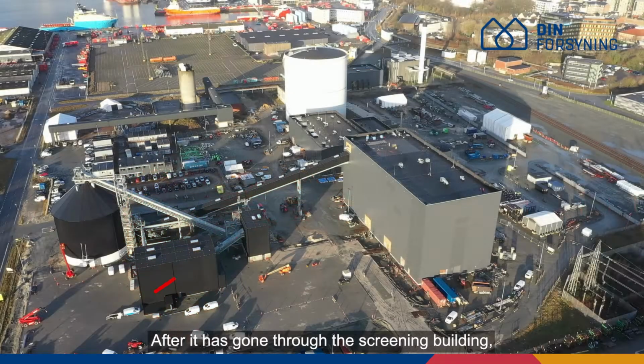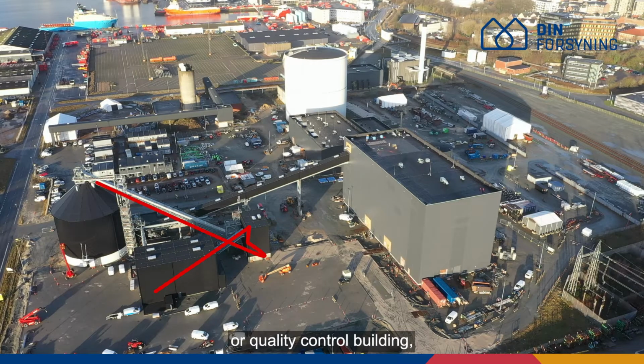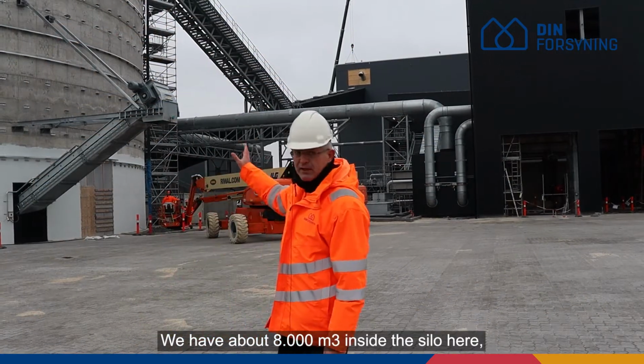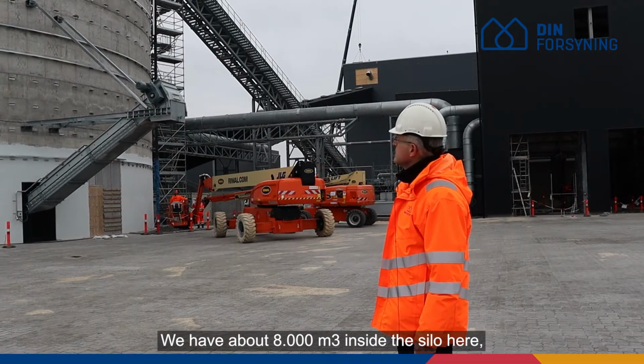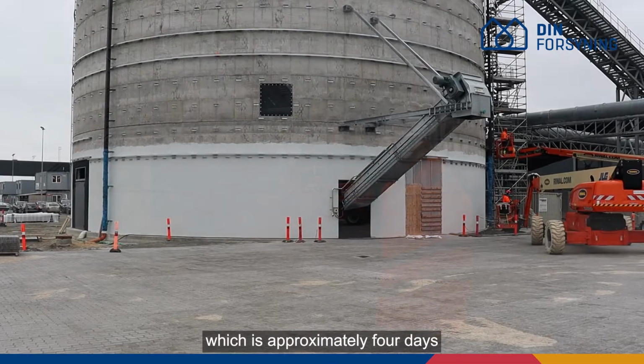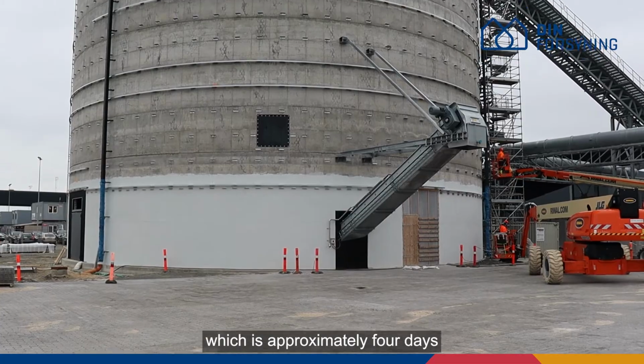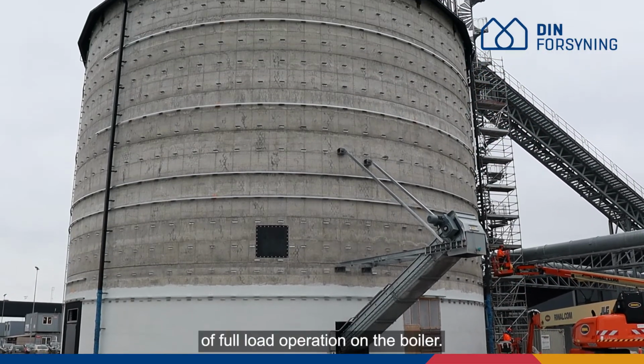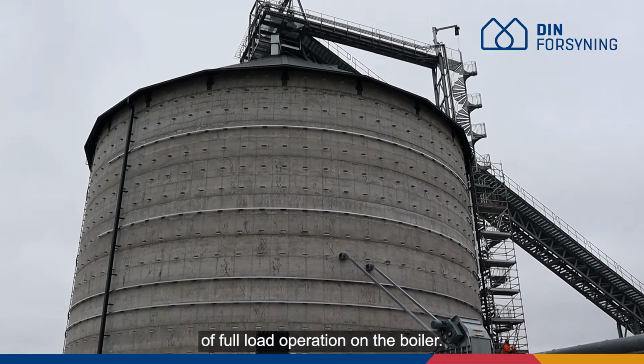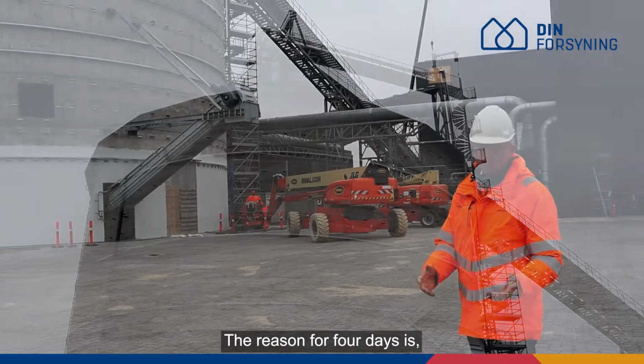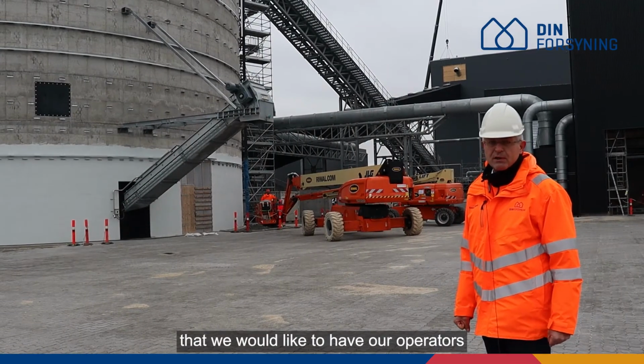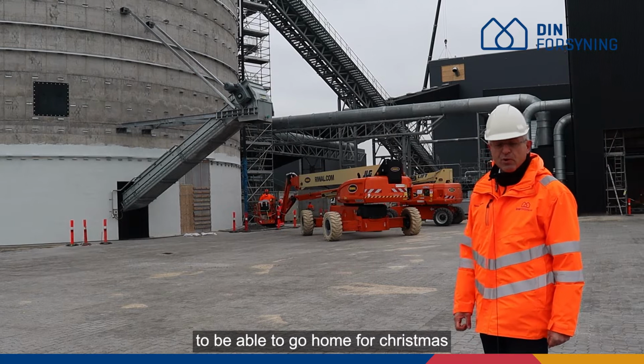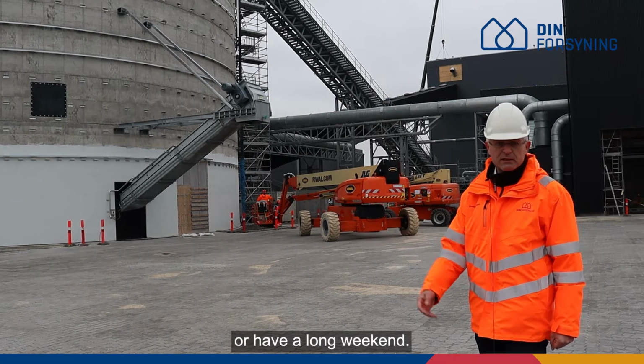After it has gone through the screening building, or quality control building, if you put it that way, the wood chip will go to our main storage, and we have about 8,000 cubic meters inside the silo here, which is approximately 4 days of full load operation on the boiler. The reason for 4 days is that we would like to have our operators to be able to go home for Christmas or have a long weekend.